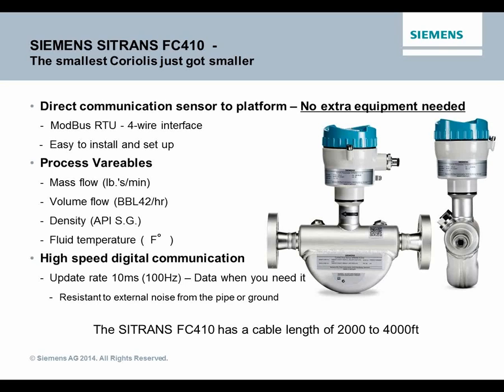Now that's not the frequency of the tube. That's the update rate. So as your fluid rate is changing very quickly, you can pick up the data at 100 hertz. It's a pretty fast update rate. Now the tube frequencies, since that question was asked earlier, I mentioned the tube frequencies can vary greatly depending on what's in them. But the highest tube frequency on our device is about 700 hertz, and the lowest is about 350. And the reason for the higher frequencies than some of our competitive meters is we find that these frequencies help mitigate some of the process noise that is typically seen in the industry today.